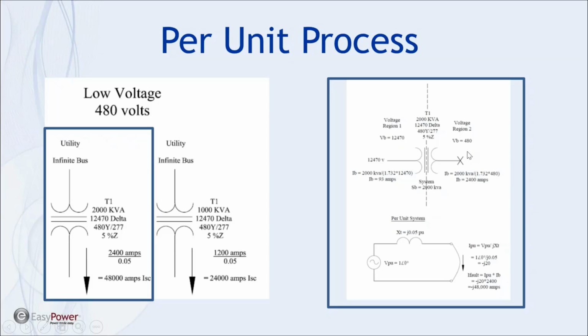representation for it here. On the right-hand side here is my approach to the per unit system. In the middle here, hopefully you can see it, I've selected an S base of 2000 kVA. When I break my systems into voltage regions, when we're doing this in a classroom setting, I ask everybody to draw dotted lines through their transformers and then break it into regions. So here we've got voltage region 1 on the 12470 side, and then voltage region 2 on the 480 side. And in this example, we're going to put a fault on the 480 volt side. Now, there's no change of base to be done in this system.